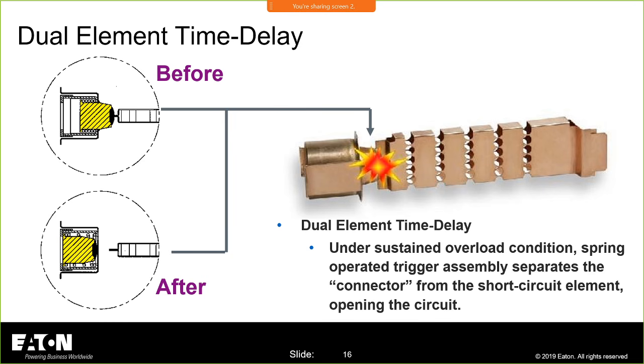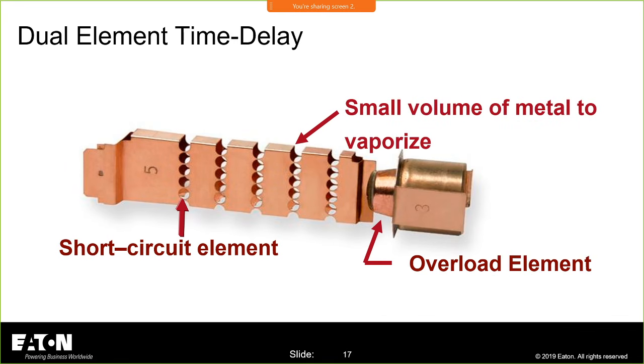But anytime you hear of, like in circuit breakers, you'll have a bimetal in there that will slowly bend, because as it gets hotter, it will start to bend. But as a fuse, you're not bending anything. You're going to slowly melt something because it's all about the physics of heating and the metals that are selected there to melt, and then it opens on the long, persistent overcurrents. So you have the overload element, which is identified where it's pointed. I don't have to draw anything.